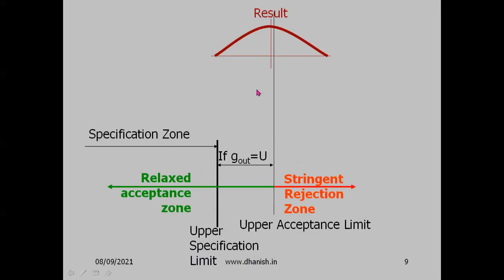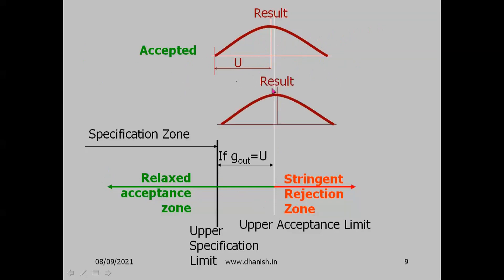If the measurement result average is to the left of the upper acceptance limit — in the relaxed acceptance zone — the product is accepted, even if there is a high probability it is outside the specification. This applies to non-critical or costly products. If the average is beyond the upper acceptance limit in the stringent rejection zone, the product is rejected.